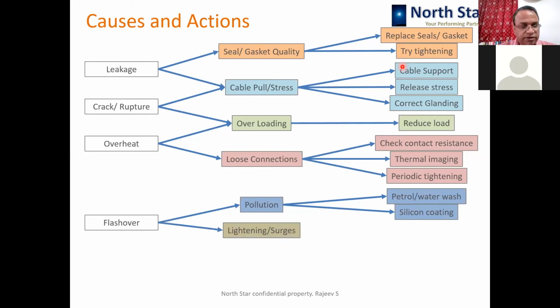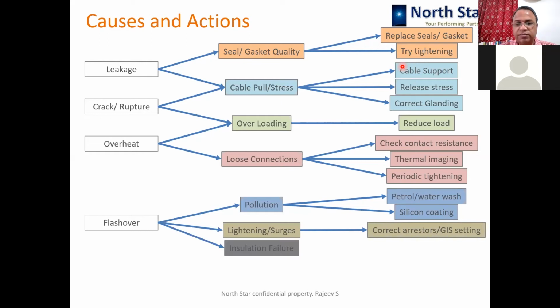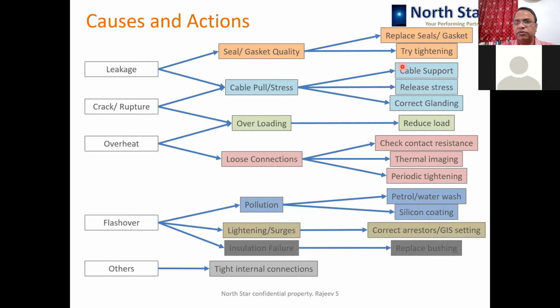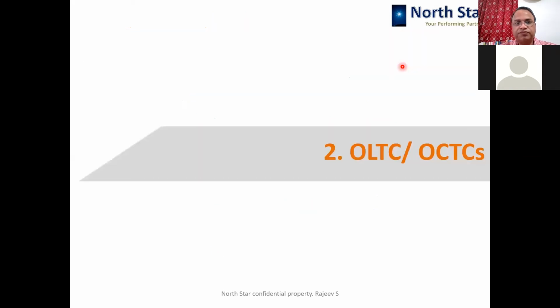Lightning surges cause the flashover, and correct arresters and GIS setting can be done. Insulation failure: if the bushing insulation itself has gone, then nothing can be done. We have to replace the bushing. Then other factors, like internal ones, there could be some issue which can be arrested with the help of the OEM.